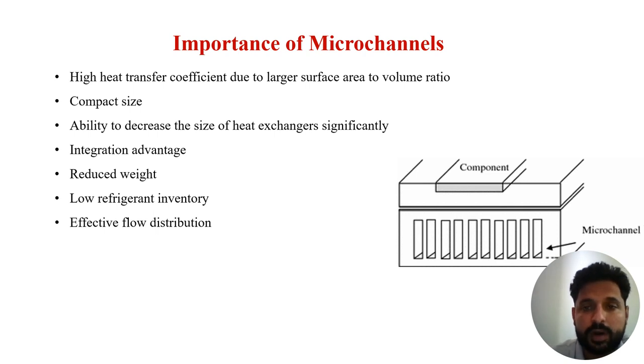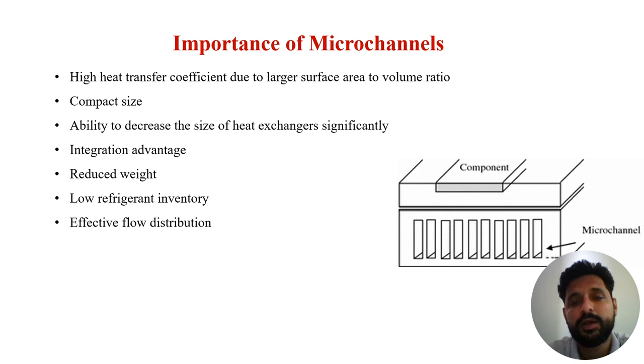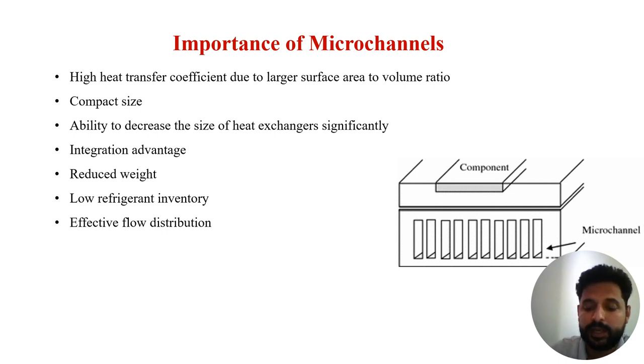The advantages of micro channel heat exchangers include a high heat transfer coefficient due to more surface area per unit volume and the ability to significantly reduce heat exchanger size because of compact dimensions. They can be directly embedded or machined into components, require less refrigerant inventory, have reduced weight compared to conventional heat exchangers, and provide effective flow distribution of the two-phase coolant across all parallel channels.